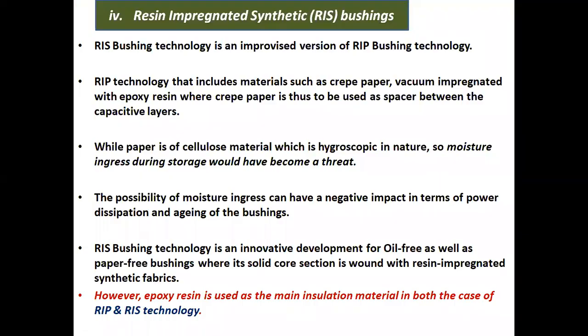Let's start with resin impregnated synthetic bushings, RIS bushings. RIS bushing technology is an improved version of resin impregnated paper bushing technology. Resin impregnated paper technology includes materials such as crepe paper, vacuum impregnated with epoxy resin, where crepe paper is used as a spacer between the capacitive layers.